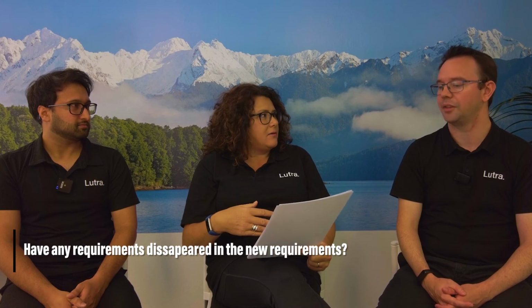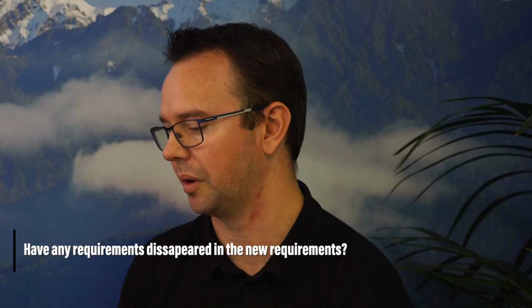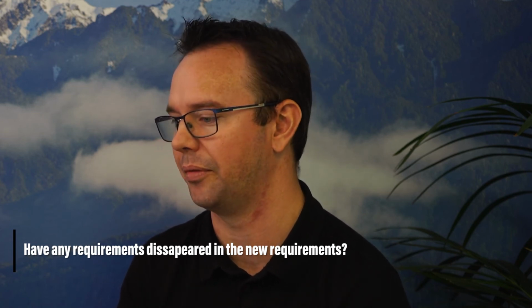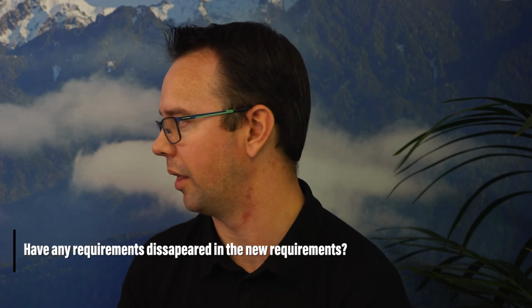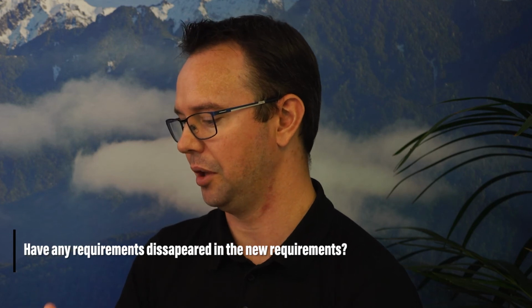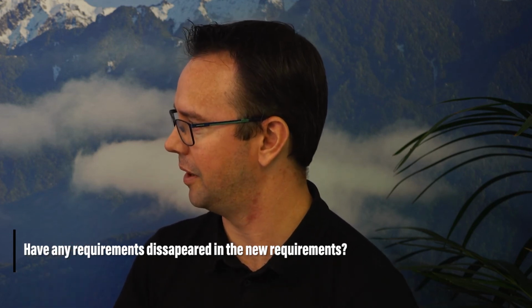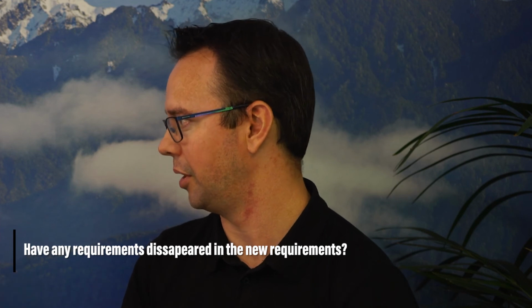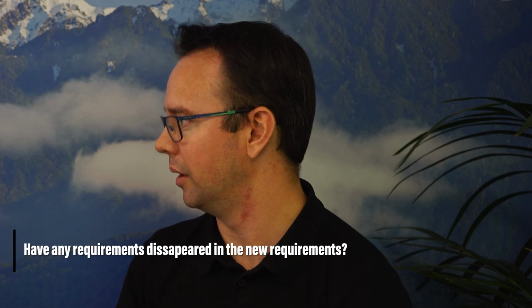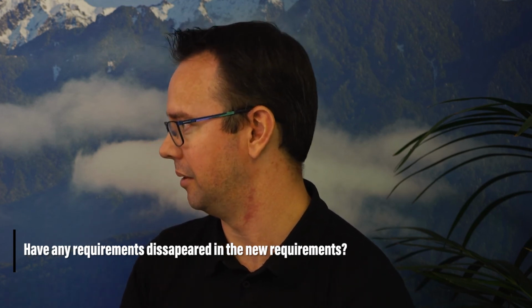Okay. So there's new rules, there's changed rules, and there's some old rules. Has anything disappeared? Yeah, so there's a few of the monitoring requirements that have changed. A lot that have been updated, and some of them have disappeared entirely. One example is that at the moment filters have a set of limits where you can't be more than a certain value for 5% of the month, 1% of the month, and 3 minutes. The 1% has disappeared. So now it's a case of 5% and 15-minute events.